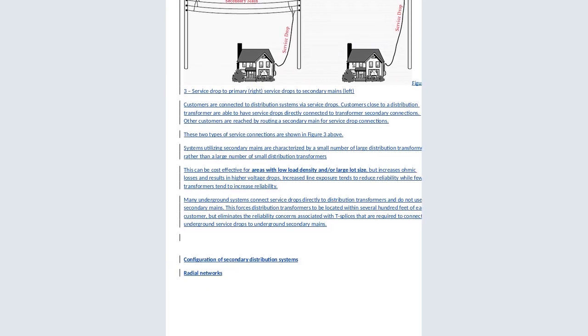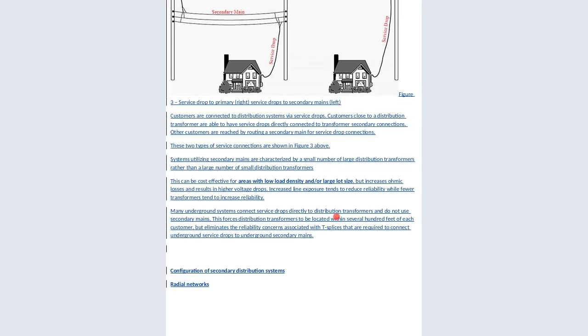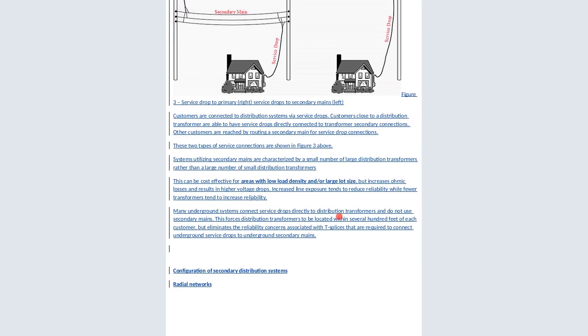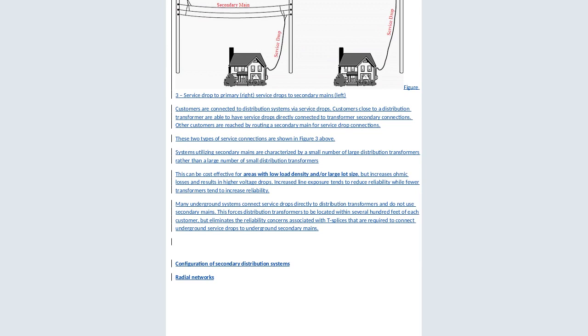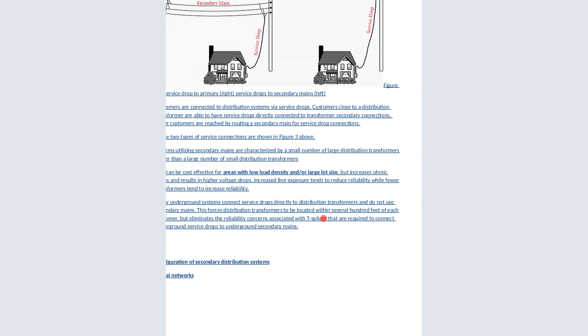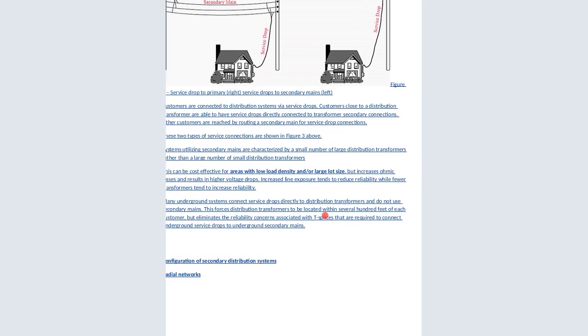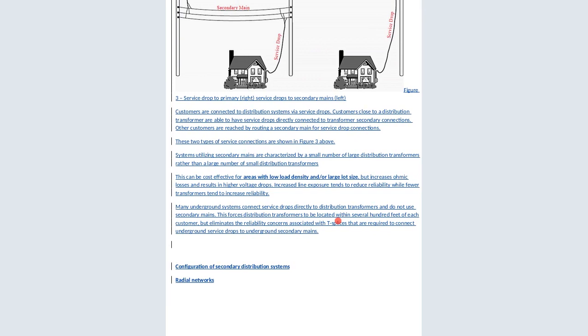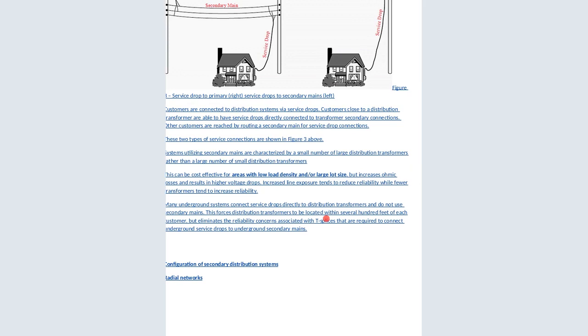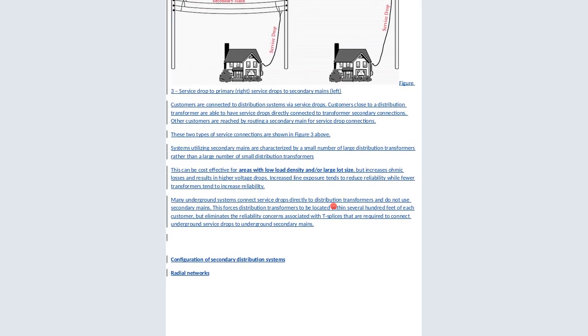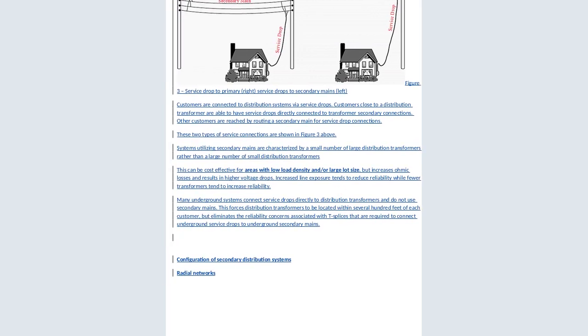You can see that figure. Now, systems utilizing secondary mains are characterized by a small number of large distribution transformers rather than a large number of small transformers. This can be cost effective for areas with low load density and/or large lot size, but it increases ohmic losses and results in higher voltage drops. Increased line exposure tends to reduce reliability, while fewer transformers tend to increase reliability.